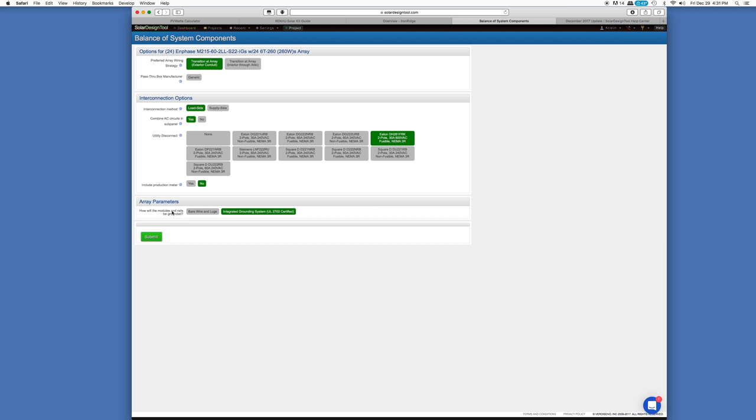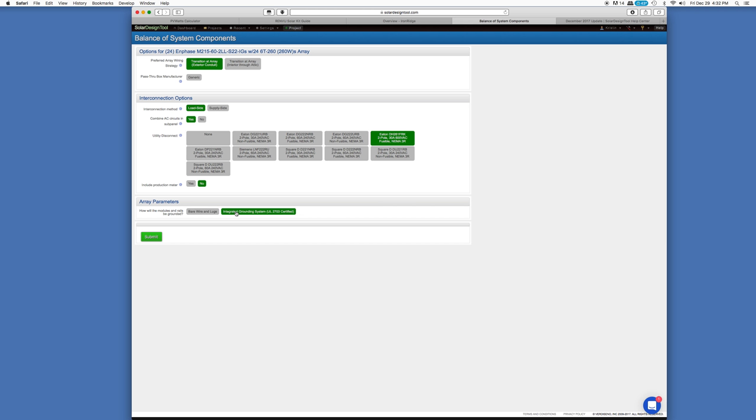So just for this example, I'm going to pick a different one. We'll use a fusible 30 amp disconnect just to show you how it's going to look when we're all done here. We are not going to have a production meter. I actually use the software from Enphase to track how much production I'm making. Here's another thing. How will the modules and rails be grounded? That is important. Grounding is very important in electrical systems, including solar. And in this case, because I'm using those Enphase microinverters that they have the integrated grounding built in and it's working with the iron ridge racking, those two together will allow me to use integrated grounding built right in. I do not need a separate big heavy cable and a bunch of lugs to connect that cable to the racking, the frame of the solar panels, things like that. But that is how many, many, many solar systems are done. Just not in this particular case. I'm going to be using the integrated grounding and we will submit this.